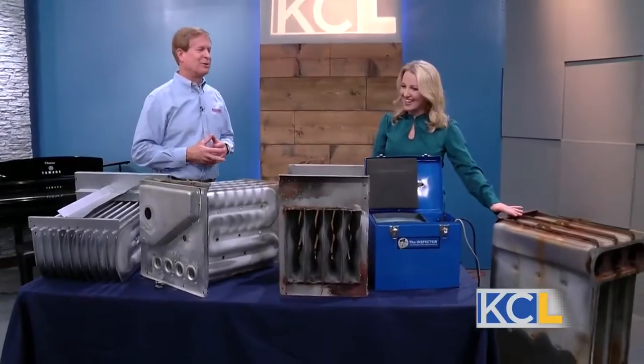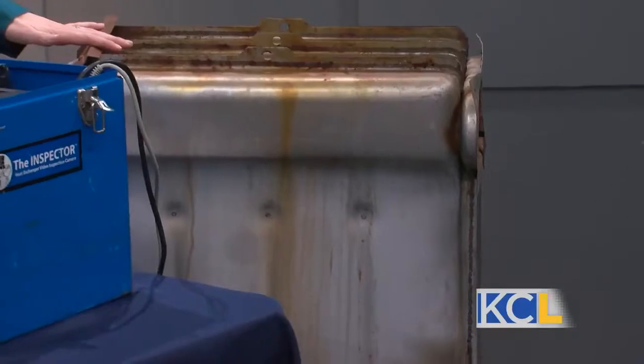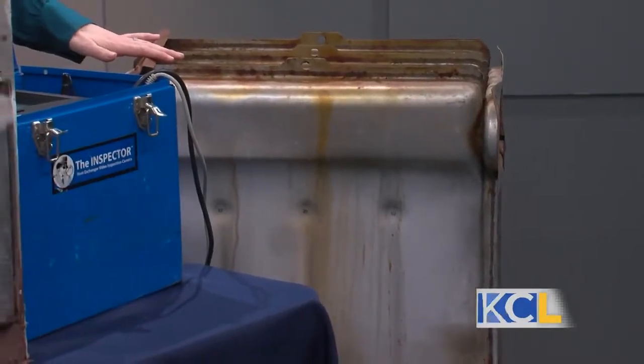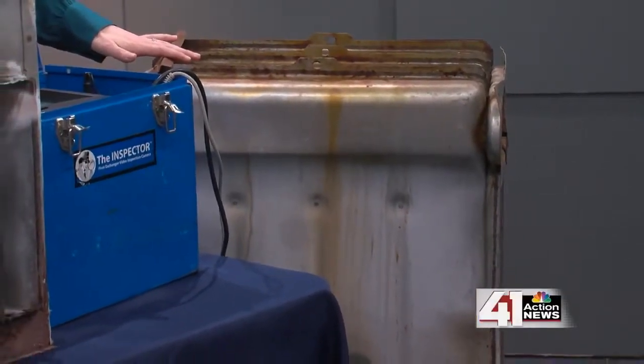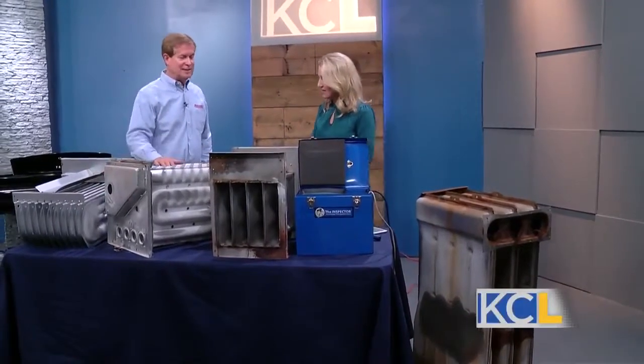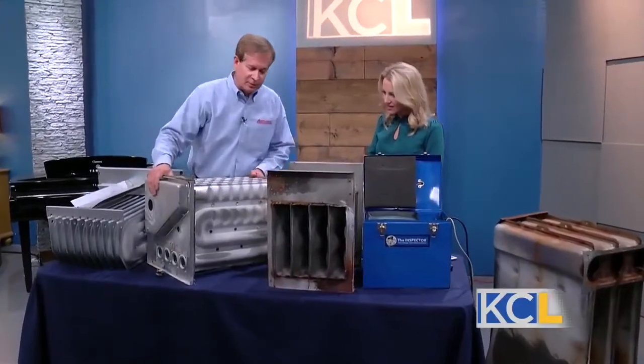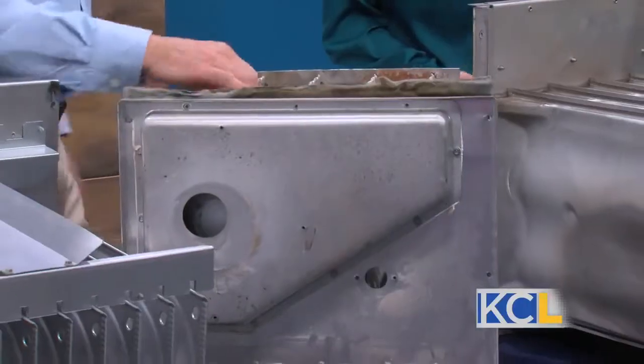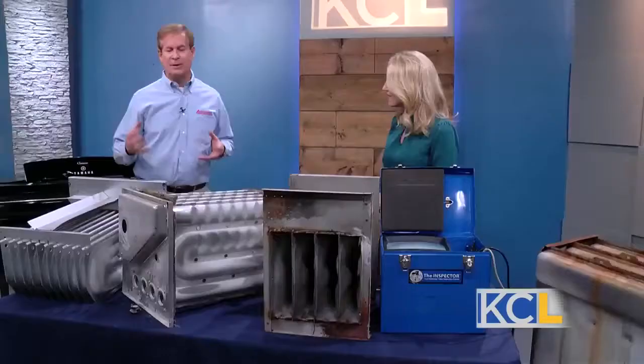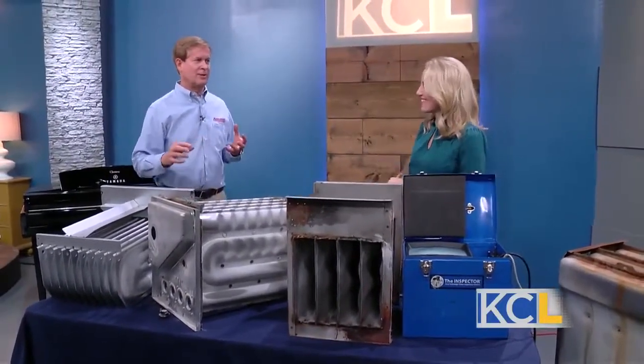This one doesn't look so good — it's a really rusty old one with a lot of rust as well as three cracks in it. That's a large heat exchanger off of an old big furnace. Today they make them with aluminized steel so they don't rust as easily, but they still rust and still crack. This one has a crack in it. Sometimes you just see a discoloration from the heat. But there's a casing around this, so they're actually hard to get to and see.